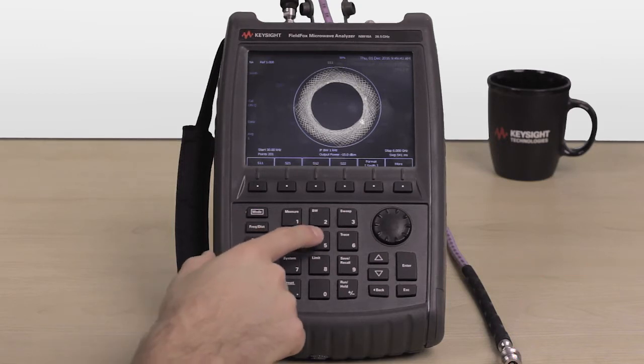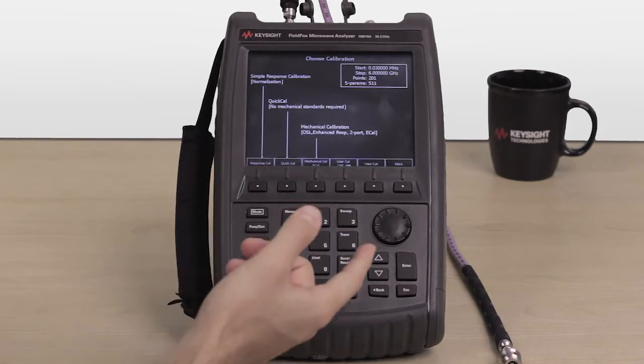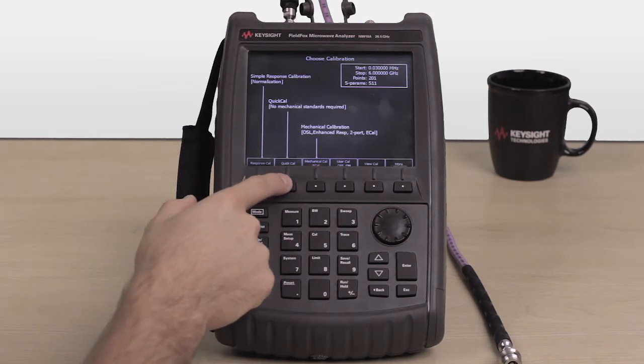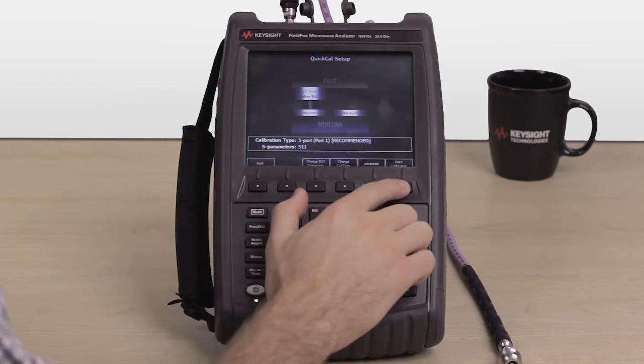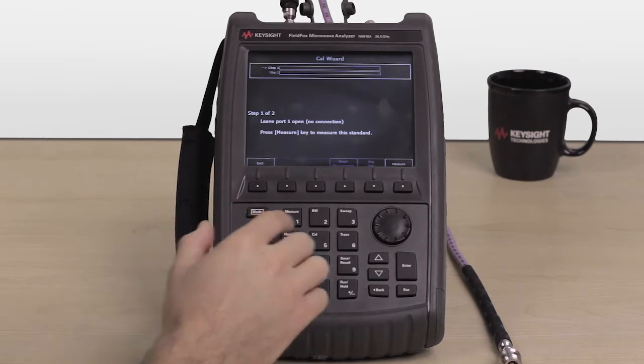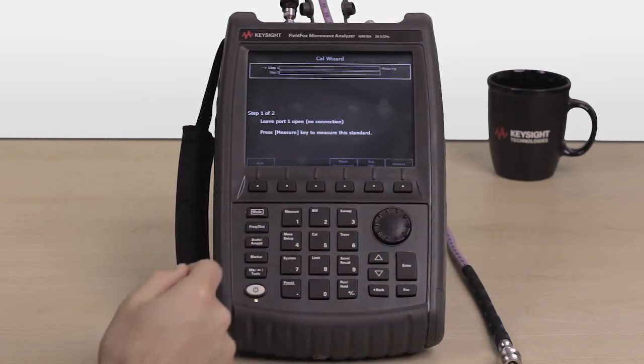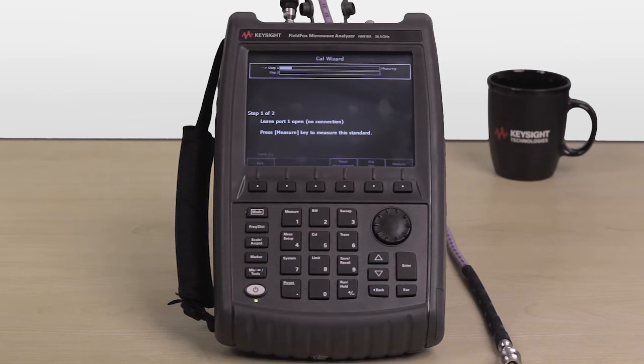We're going to need to go to Cal and we're going to choose Quick Cal since we don't need any mechanical standards. Then go to Start Calibration. We have an open connection so we're going to press Measure. And what we're going to expect to see is our impedance shift from all over the place to around infinity ohms.